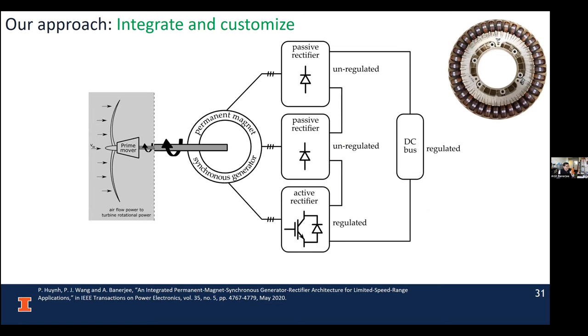Instead of treating the machine as a three-phase output, we say it's a multi-phase machine. Instead of having only 3 wires coming out of the machine, imagine 9 wires coming out, where each of these ports is 3-phase. We connect each port to a passive rectifier, except one, which is connected to the active rectifier. We take the DC bus out of each individual port and stack them together to create the DC bus—that's why we call this an integrated generator rectifier architecture.